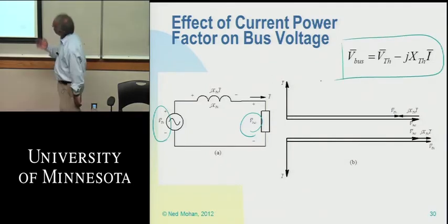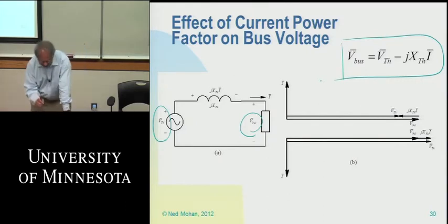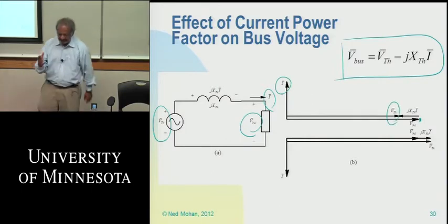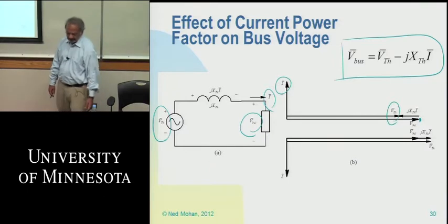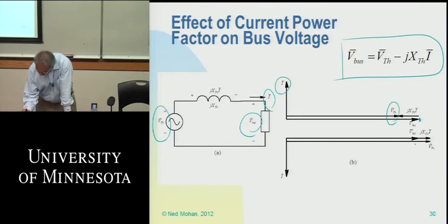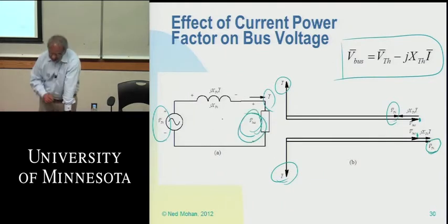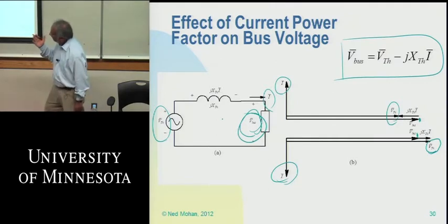Showing it in phasors: for a certain bus voltage, if the current drawn is leading, the sending end voltage is actually smaller than the bus voltage. However, if the current is lagging, like connecting an inductor, the sending end voltage has to be larger than the bus voltage. So you can see the effect of leading versus lagging current makes a real difference.